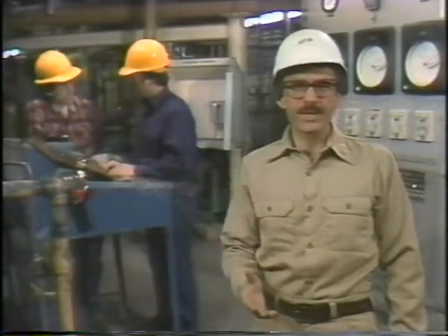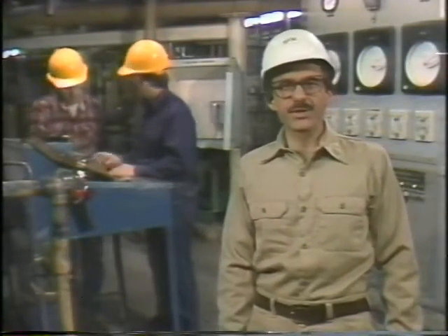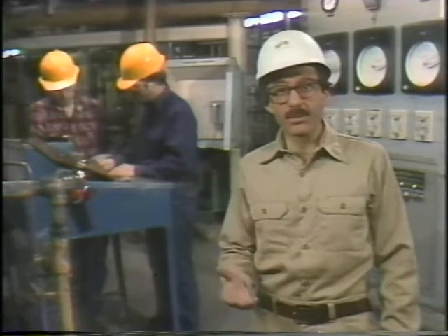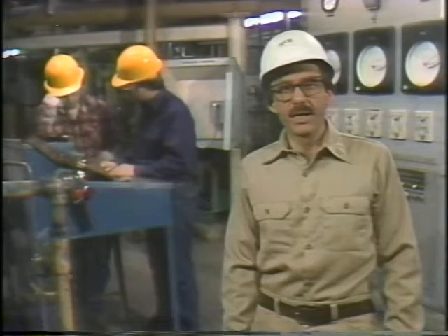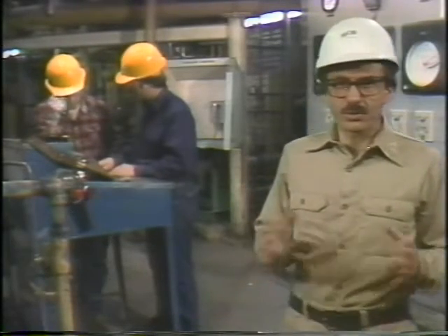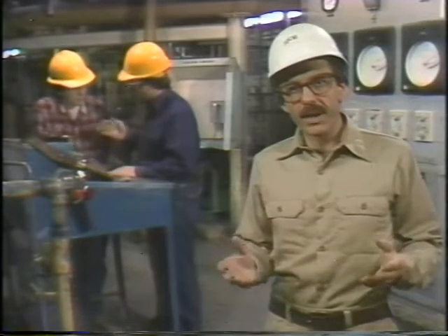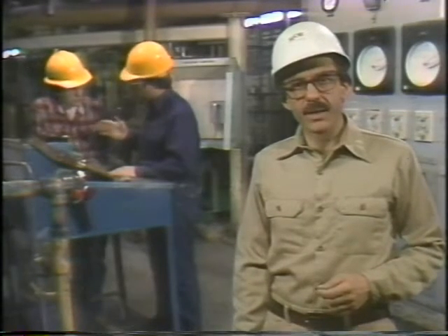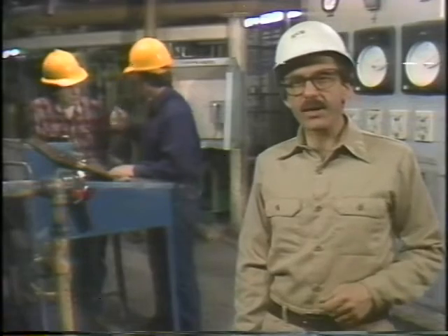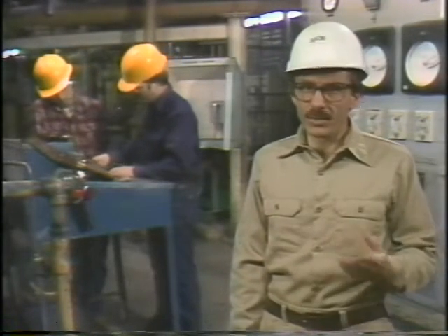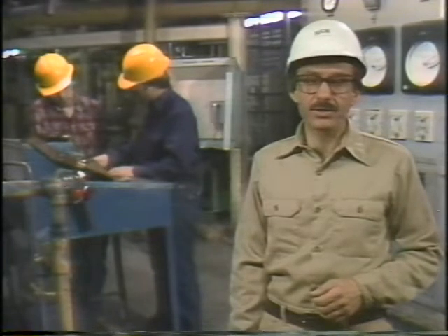So far, we've seen a procedure for troubleshooting instrument systems. And we've seen Bob use the procedure in troubleshooting a problem in the feedwater control system. As you remember, Bob was able to locate a problem in the feedwater flow transmitter, repair it, and restore it to service. But when the operator put the system back in automatic, even though the feedwater and steam flow were okay, the drum level indication remained unchanged.